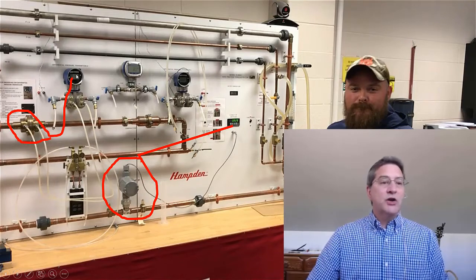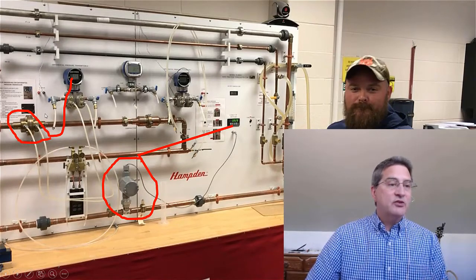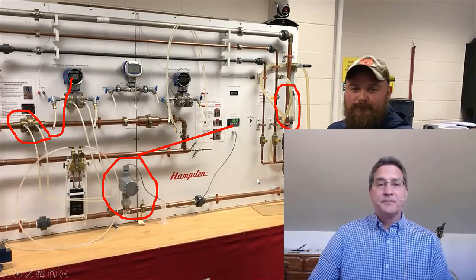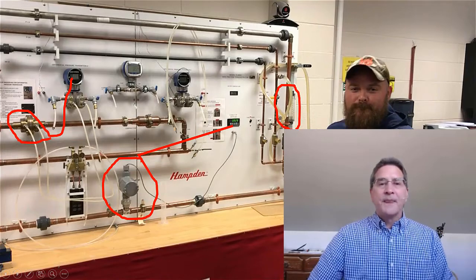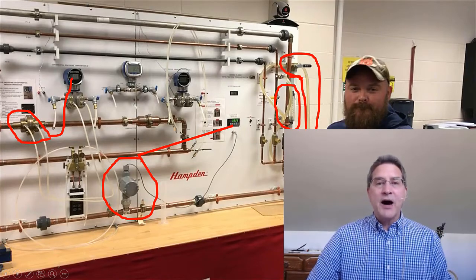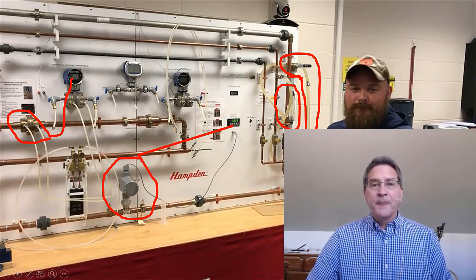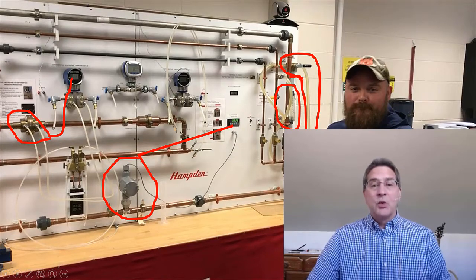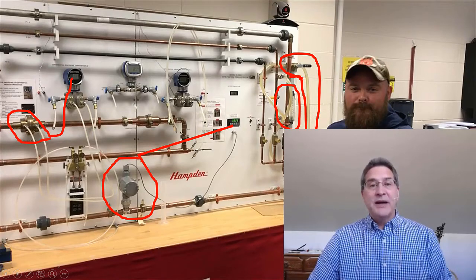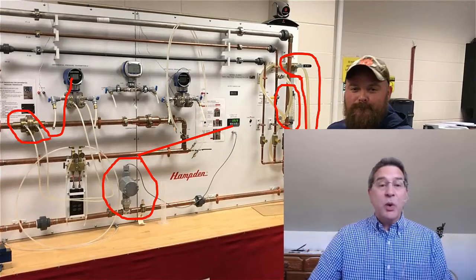It has what's called an orifice plate, which he pointed out. It looks at the delta pressure here and displays it, and you can calculate flow. It has what's called a rotometer right here. And then it has this valve that we can close, so that instead of flowing through here, the water flows out of this tube. So we can do a direct capture. We can capture the water, time it, and then calculate gallons per minute from that. That's what we want to do.